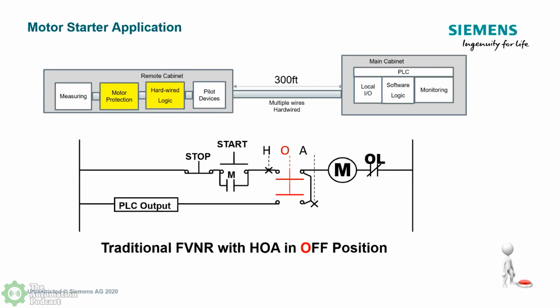But this is a standard hand-off-auto in the off position motor starter that you would encounter in multiple plants throughout the nation. You can see that there's a PLC output so that when it goes to auto, it will turn on the motor being controlled by the DCS system or the PLC. And then you see that you have a sealing circuit right here, which is an auxiliary contact that would be with the NEMA starter or the IEC contactor.